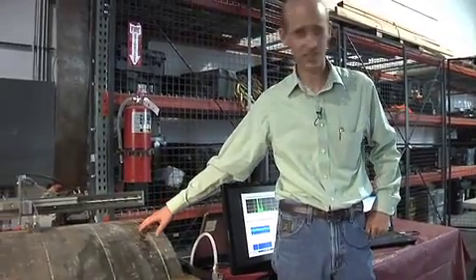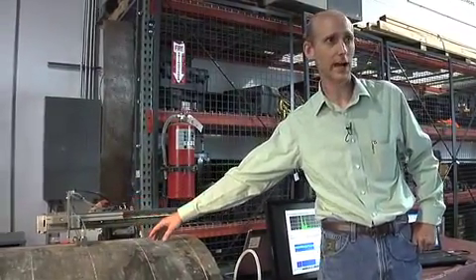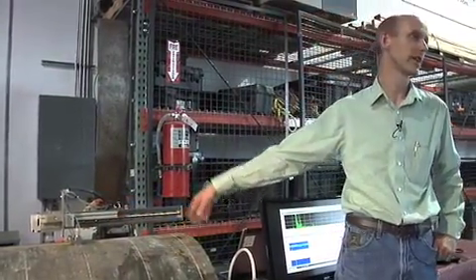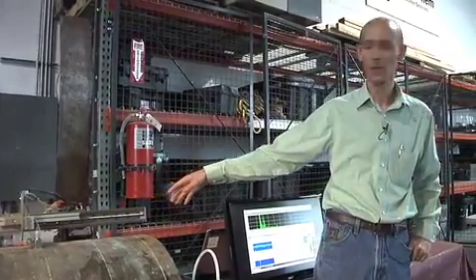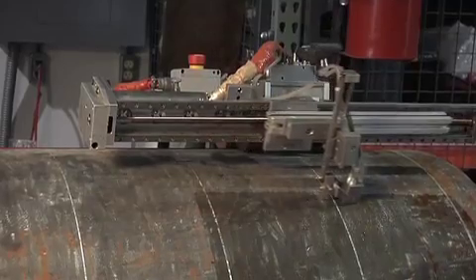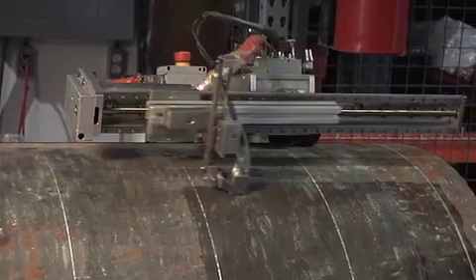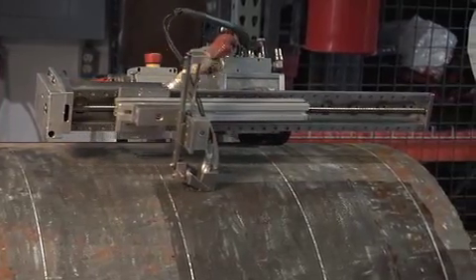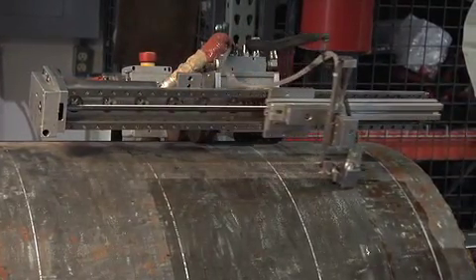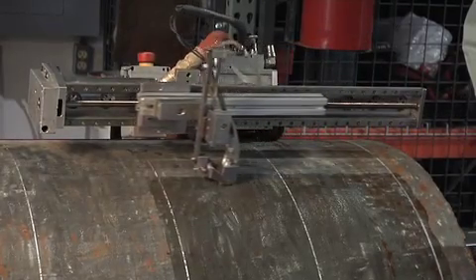Now, this scanner, it's set up for a 16-inch run across this way right now, but we can go up to 48 inches at a time. We just have one transducer on there. We've had these set up where we have four transducers going. So, if I were to take 12-inch in between each transducer, I could collect 48 inches in the same amount of time as I could collect 12 inches.